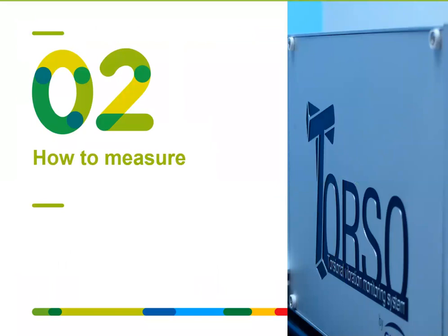So this was an overview of the theoretical side. So to remember is that torsional vibrations are excited typically by the grid. It's a twisting motion of the shaft line superimposed on the steady state rotation. Frequencies typically are in the range of 6 hertz to 20 hertz, depending on what type of shaft line you have, gas turbine, steam turbine. And the higher the frequency, the more complex, and typically the harder it is for the grid to transfer energy in the mechanical part. So typically the most prone ones for damage or for torsional excitation are the lowest ones. These are also the ones most prone for any subsynchronous resonance phenomenon or subsynchronous torsional interaction.